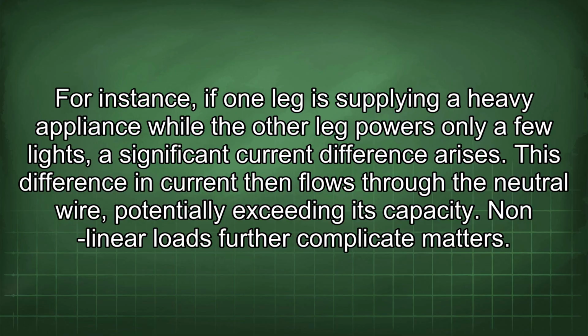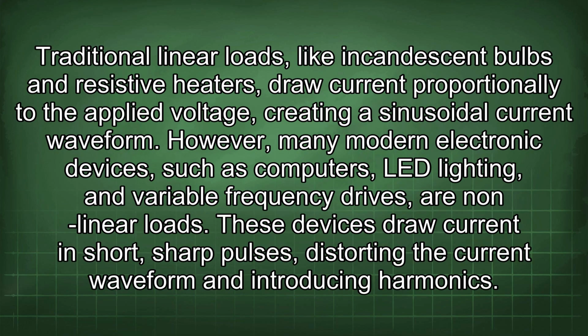Nonlinear loads further complicate matters. Traditional linear loads, like incandescent bulbs and resistive heaters, draw current proportionally to the applied voltage, creating a sinusoidal current waveform. However, many modern electronic devices, such as computers, LED lighting, and variable frequency drives, are nonlinear loads. These devices draw current in short, sharp pulses, distorting the current waveform and introducing harmonics.